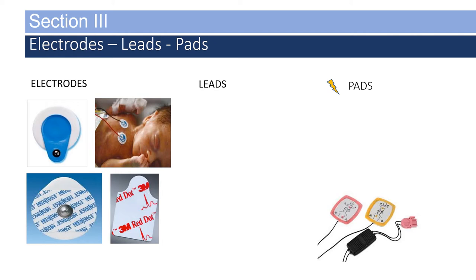Electrodes come from the manufacturer in sealed bags. Once you open the bag, if there are electrodes left within the package, the bag should be folded over on itself and sealed in a Ziploc bag. Open bags of electrodes are usually good for approximately 30 days after opening. Don't preload the electrodes on the wires, as this may alter the integrity of the electrodes as they dry out sitting in the back of the ambulance.